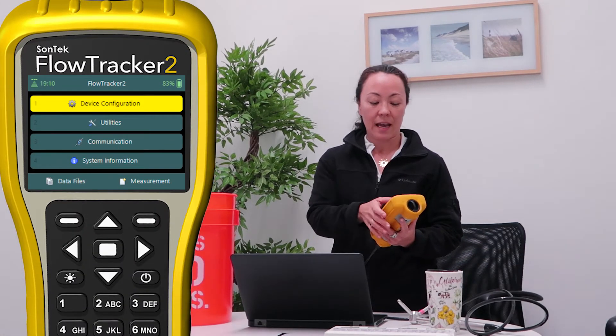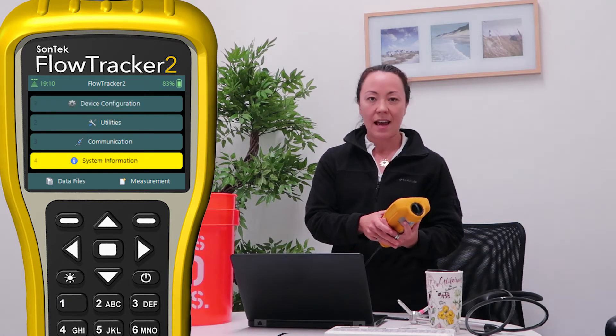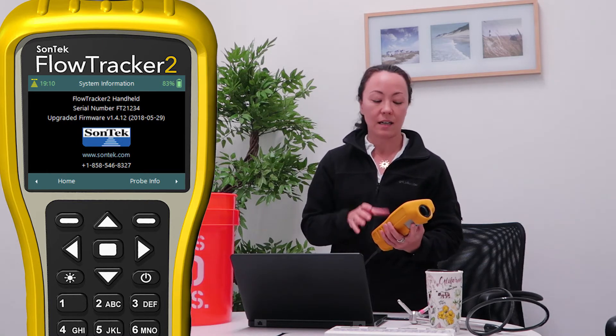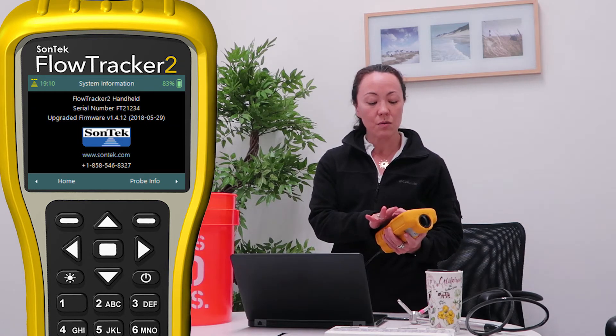My FlowTracker is booted up and I'm at the home screen. I'm first going to go down to system information and just make sure that the latest software and firmware are uploaded to your instrument, because we're always improving the software and firmware and you want to make sure that's to your advantage. If you don't know if you have the latest version, go to SonTek.com to download it, or just check the version number shown on the screen — if it matches what the website says, you're good to go.